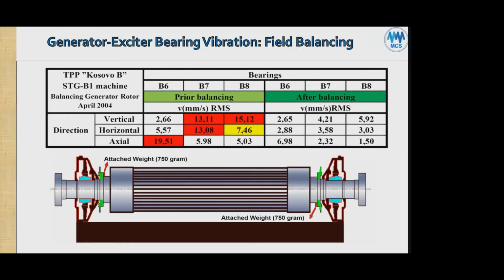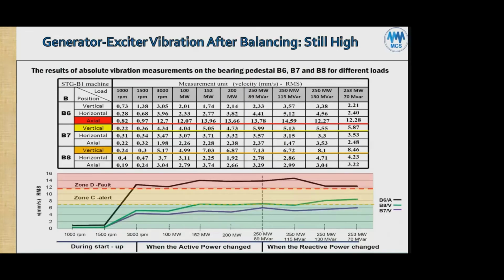And you can see they attach 750 gram on one side and 750 gram on the other, according to their balance program. Okay. So as we can see here, the vibration on bearing B6 is reaching the highest. On the axial, it reached 14.59 after startup. From the left to the right, we have the speed at 1,000 RPM, 1,500, 3,000 RPM, and then after 3,000 RPM, loading with 100 megawatt. Remember, it's a 339 megawatt rated. So they loaded it with 100 megawatt and took a reading, then 152 megawatt and took a reading, then 200 megawatt and took a reading, and then 250 megawatt, and then 250 with higher MVAR.